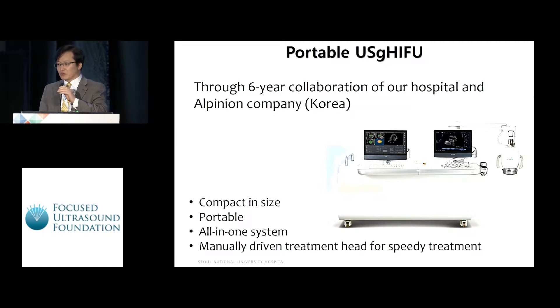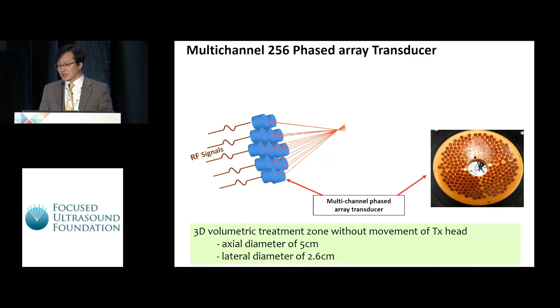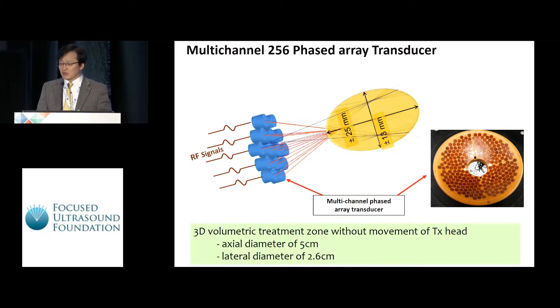We developed a new portable ultrasound-guided HIFU for the abdomen through a six-year collaboration between our hospital and Alpinion company. Different from previous ultrasound-guided HIFU systems for the abdomen, it is compact in size, portable, and an all-in-one system. It has a manually driven treatment head for speedy treatment, and a multi-channel 256 phased array transducer using electronic steering. It provides a 3D volumetric treatment zone without movement of the treatment head, with an axial diameter of 5 centimeters and lateral diameter of 2.6 centimeters, which is very helpful to reduce treatment time.